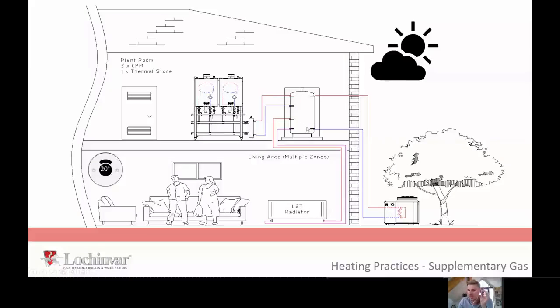Okay, so the heating schematic we just looked at, this is an application basically doing exactly the same thing as we've just described. What we've got is the heat pump, and its job in life is to maintain a buffer vessel at 50 degrees. This is a case study. It's called the Cali White Care Home. It's on Lochinvar's website. Check it out if you like, but it's a heat pump working in tandem with a couple of boilers. So the heat pump serves a thermal store, maintains it at 50.